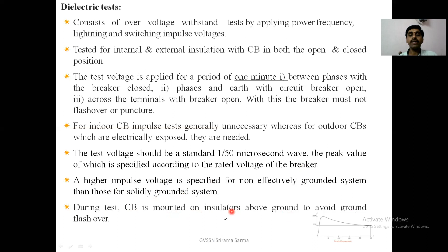The 1/50 microsecond wave is applied, the peak value of which is specified according to the rated voltage of the breaker. So this peak voltage depends upon the rating of the breaker. A higher impulse voltage is specified for a non-effectively grounded system. Non-effectively grounded means they are not solidly grounded systems, that is, resistance grounded, reactance grounded, etc. So compared to the solidly grounded system, for a non-effectively grounded system, a higher impulse voltage is applied. During the test, the circuit breaker is mounted on insulators above ground to avoid ground flashover.